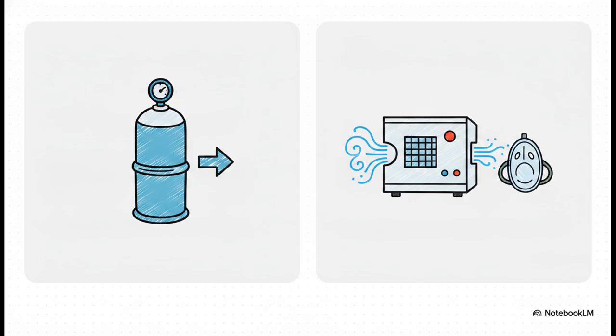Let's compare 2 totally different solutions for delivering this gas. While an oxygen cylinder holds a finite amount of pressurized gas, meaning it eventually empties and has to be replaced, an oxygen concentrator is a totally different beast. It uses an internal compressor and specialized molecular sieves to continuously pull in regular room air, trap the nitrogen, and pass concentrated oxygen straight to the patient. It's incredible when you think about it. It literally creates a limitless medical supply directly out of thin air.